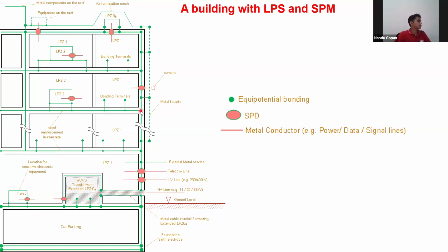All of it is steel reinforcement in concrete. So what happens if you see this picture clearly? First bonding, then earthing - there is a foundation earth electrode. The transformer has some bonding terminals here and here. It is connected to the steel reinforcement in the concrete, and the transformer's body, and probably the neutral, is connected there too. It is connected to the steel reinforcement in the concrete, and then connected to the foundation earth electrode. So everything is perfect, very good.